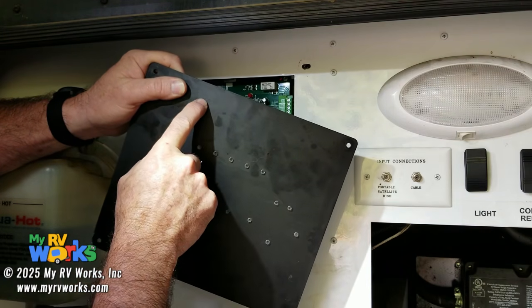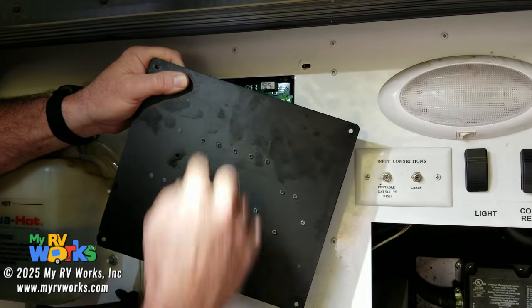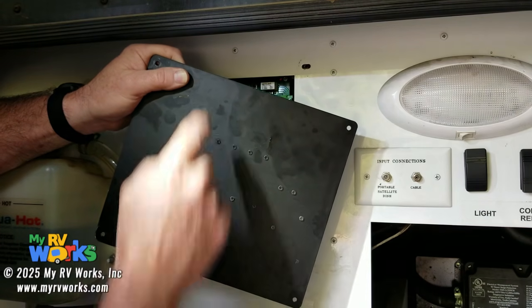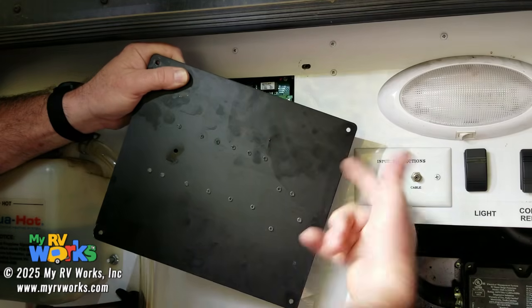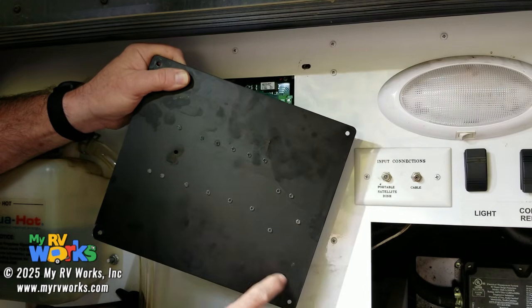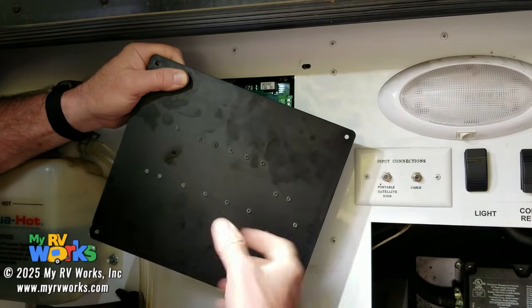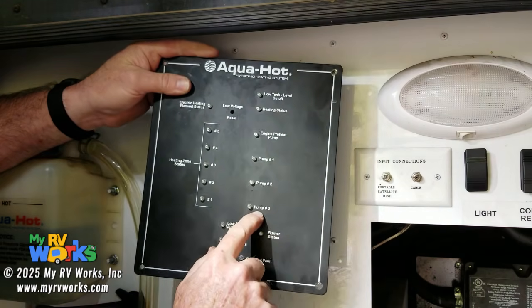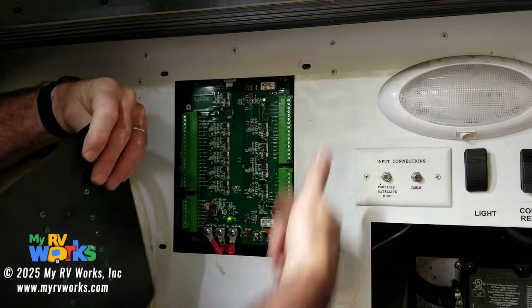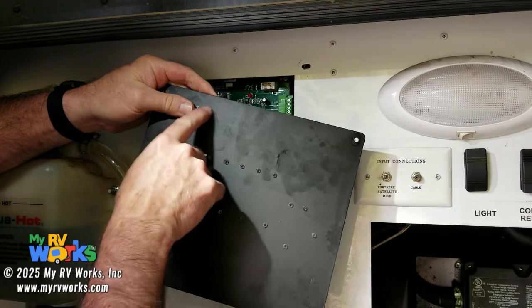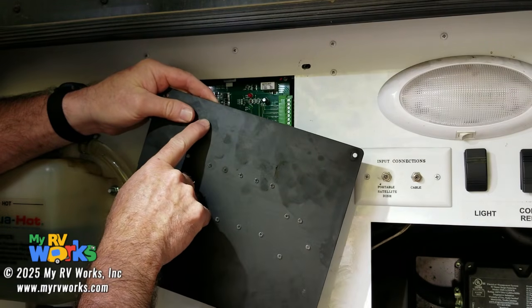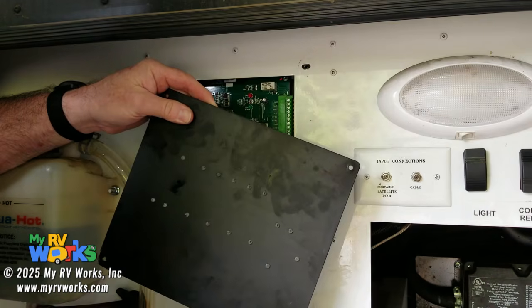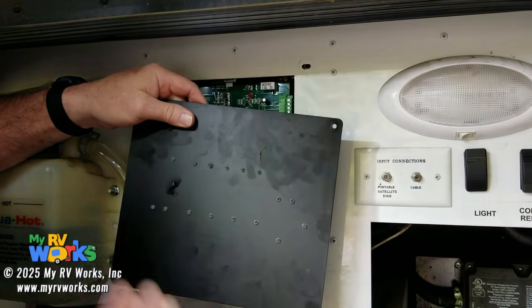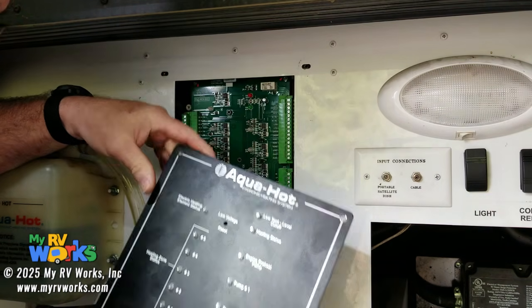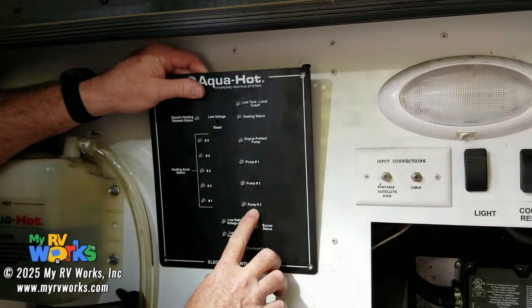So the control thermostat's up here, the burner's down here, the stratification of the water, maybe it's hotter down here than here. So there's a pump that takes the fluid from the top corner to the bottom corner and just stirs the tank. That's pump 3's job. So pump 3 is my stir pump. It's just stirring my tank so that I can get an accurate reading way over here of what the boiler antifreeze in here is. About 6 gallons plus or minus of boiler antifreeze in my tank. So pump 3 is my stir pump.